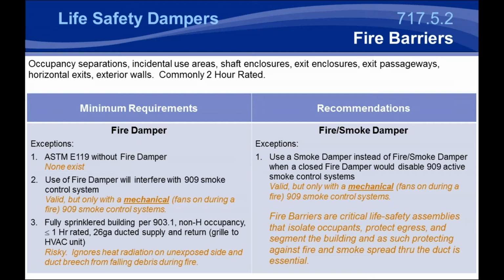Now, because of that, and because you've now got the added cost of an actuator supplying electricity and smoke detection needed, as well as indication for this damper, for a minimal cost, you can change that to a fire smoke damper. And the reason we recommend that is these are 2-hour rated or less barriers that are critical to isolating fires and keeping exit enclosures and shaft enclosures intact for the entirety of the emergency, to allow all the occupants to exit the building or shelter in place in, say, a horizontal exit while firefighters and first responders are attending to the emergency and making sure everyone makes it through the emergency safely. Because of that, we recommend the fire smoke damper requirement for two reasons.